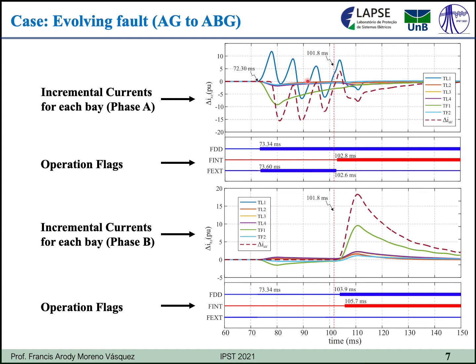Here is the result corresponding to phase A, and here is the result corresponding to phase B. Here it can be noted that after the external fault inception, the signal whose polarity is opposite to the rest is only that of feeder TL1, the blue line. In this case, the external fault is recognized and the operation relay is blocked. Nevertheless, when the external fault evolves to an internal fault, the polarity of the incremental differential current becomes the same as the initially faulted signal here. So the internal fault is recognized.